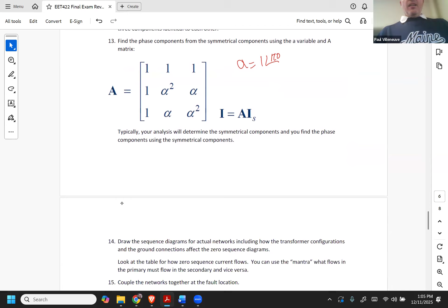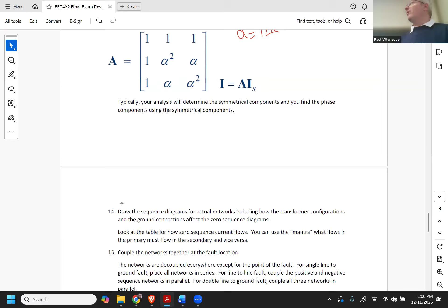And for what we're trying to do in this class, we will typically put these sequence networks together, solve for the currents in symmetrical component land, and then calculate what the phase currents are, because the phase currents are the actual fault currents. So we built some sequence network diagrams, and it was pretty easy for generators, motors, and regular old loads. They would have maybe a power source in the positive sequence and then the impedance, or just the impedance in the negative sequence. Easy peasy. But when we had a transformer, positive and negative sequence were the same. They were just impedances, but zero sequence was a function of can ground fault current flow. And so you really need to look at those diagrams to make sure, am I able to have ground fault current? So if the Y is there, you got to look and see what's connected to the neutral. If the delta is there, you have to see if there is a Y. If there is a Y, can the neutral current flow?